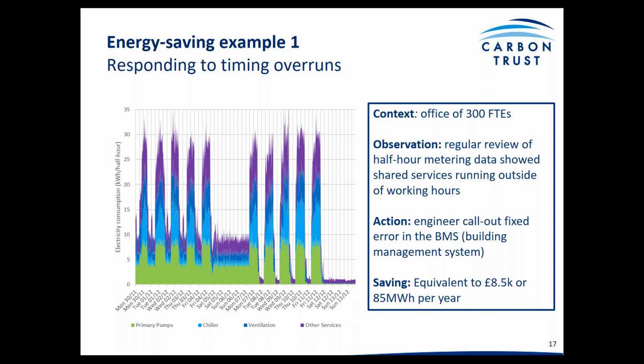This resulted in a substantial amount of energy usage out of hours, especially through the main circulating pumps. This was identified through routine checks on the half-hourly data, and the issue could clearly be seen, whereas with manual meter checks you would not be able to identify this out-of-hours consumption or pinpoint the cause. This saved approximately 8.5k a year, and they continue to monitor this.